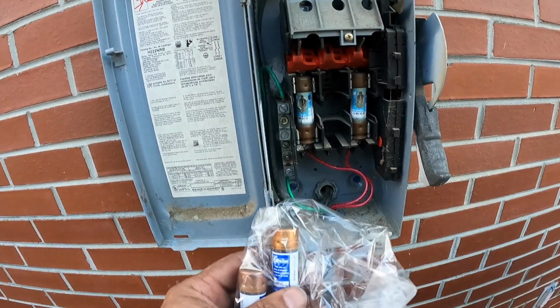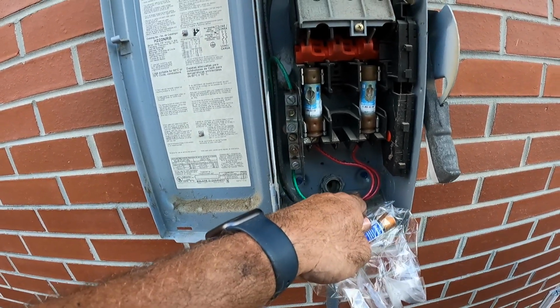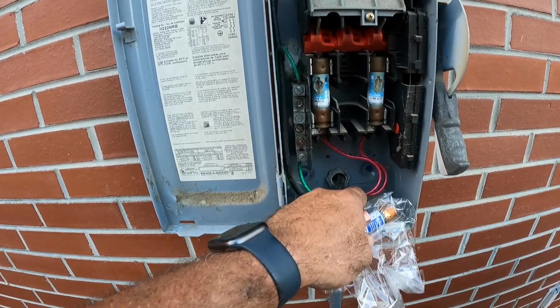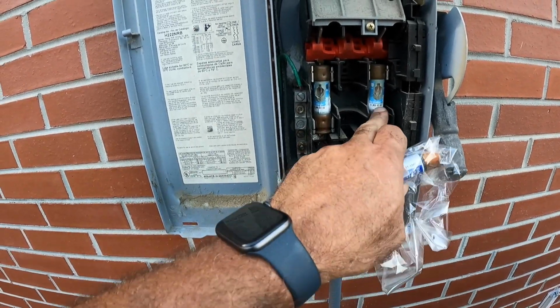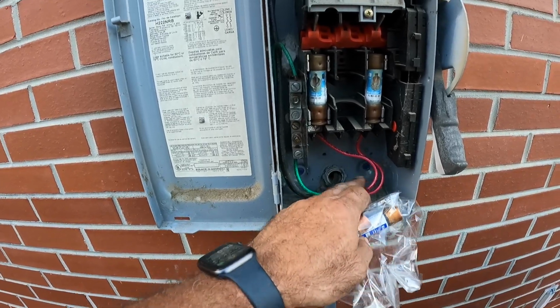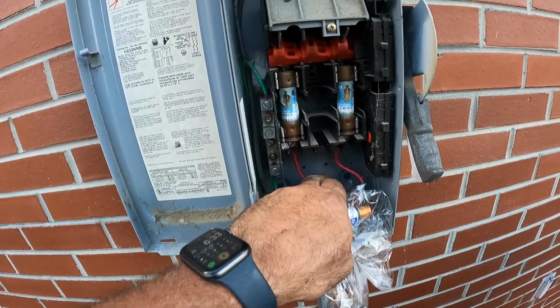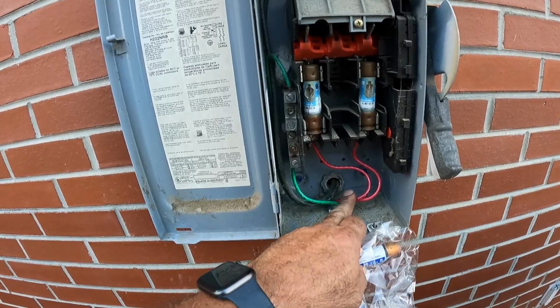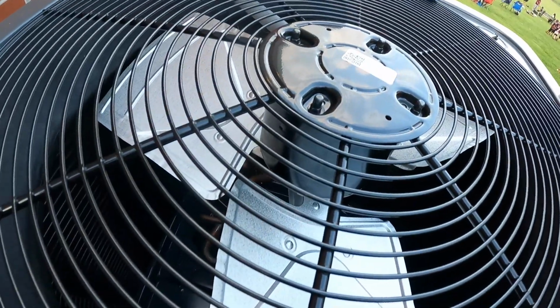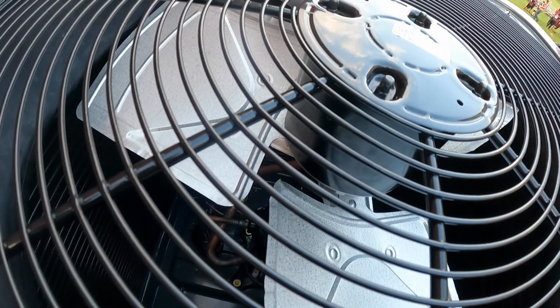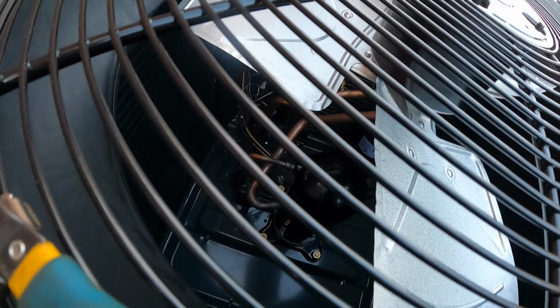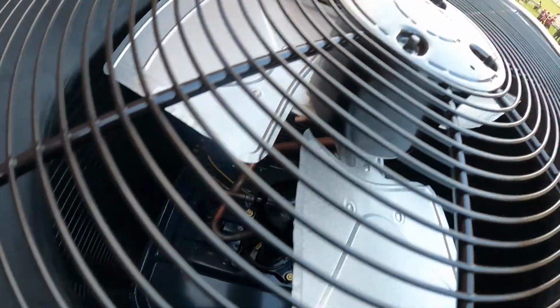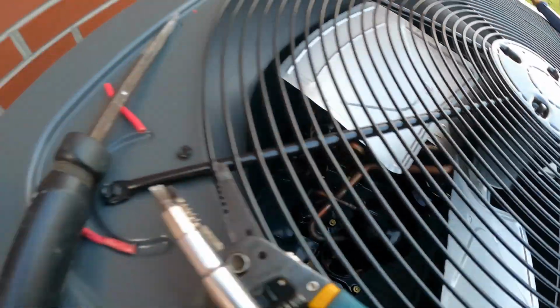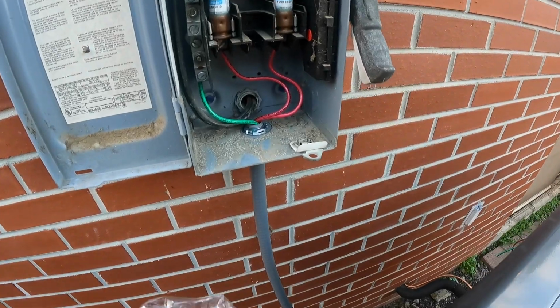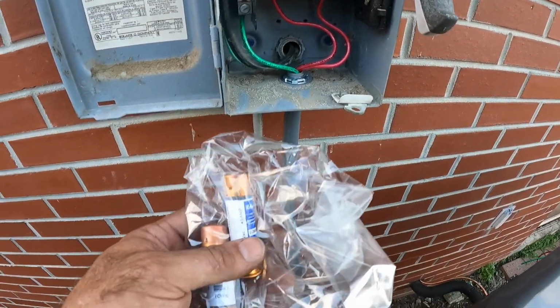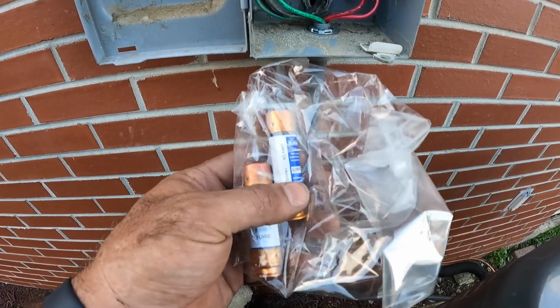A lot of people say, no, you've got to size the wire according to the fuse, but you don't, not on heat pumps. It's a special exception. The fuses protect the heat pump, and they need to be a little bigger because of the locked rotor when that compressor starts. What really protects this wire is that both these motors, the compressor and the fan motor, have a thermal cutoff in them. If they start to pull too many amps or get a little warm, they shut down. So it's in the NEC. I'm not going to tell you where to go find it, but I can tell you that it's out there. I'm sure there's lots of good videos on the internet about it.